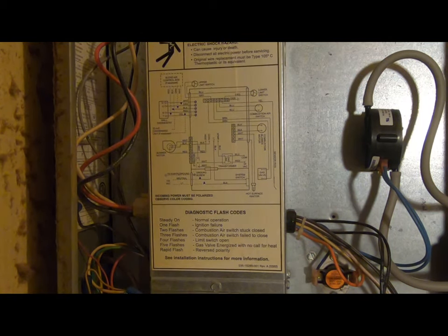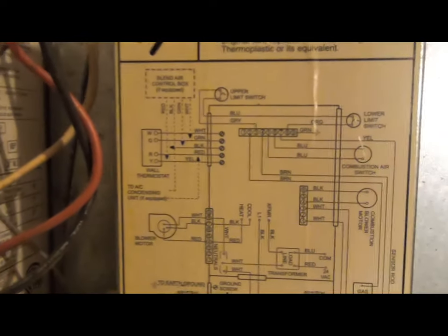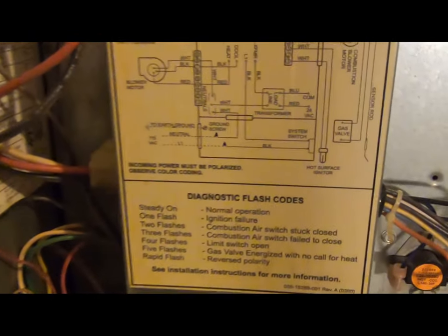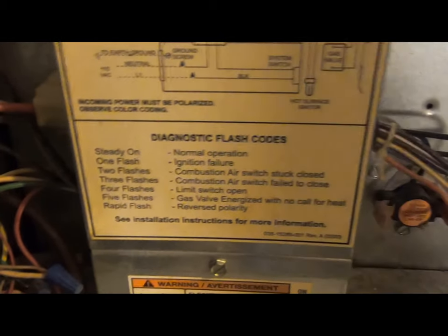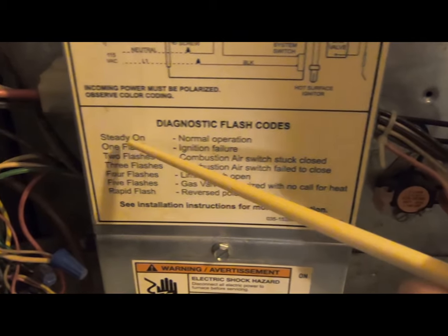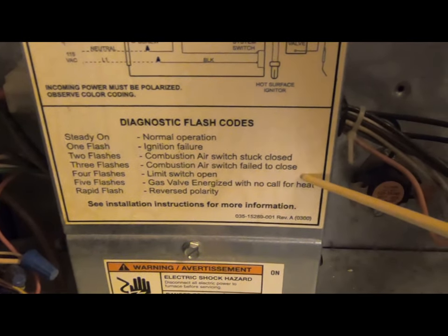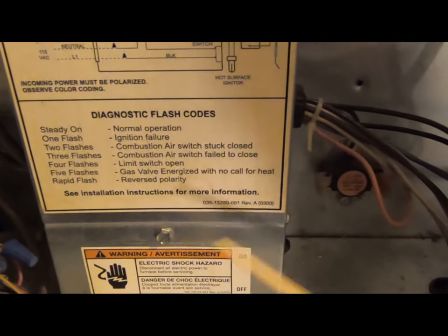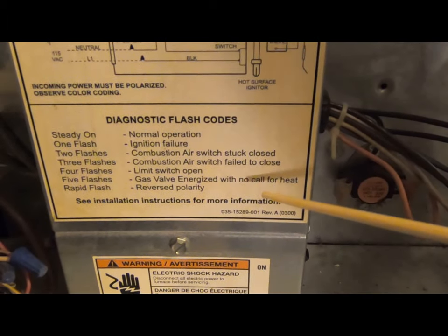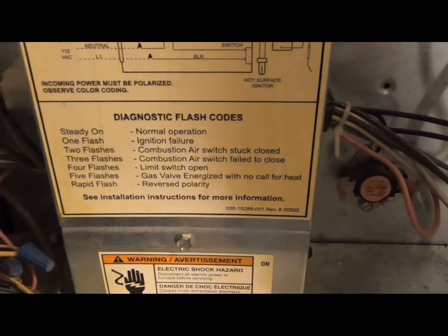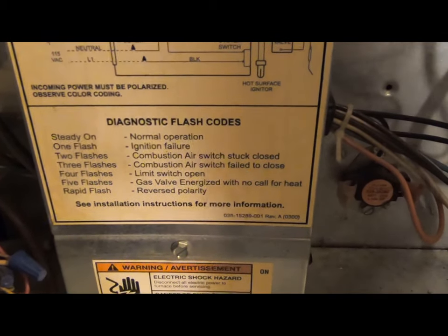Alright, now in here, this is our diagram. And as you can see there, three flashes, which is what we got, is combustion air switch failed to close. This is a chopstick, not a Harry Potter wand. Three flashes, combustion air switch failed to close.